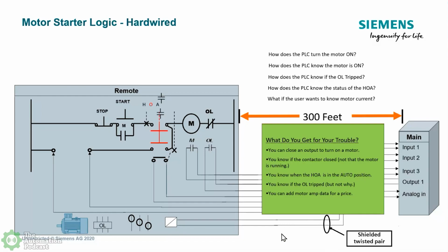So in the case of a conveyor belt, your Lovejoy coupler might have sheared, the motor's turning, so everything's fine because he sees current flowing. But is it truly turning the application that you've connected that motor to? So let's say that Lovejoy coupler sheared and the motor's turning fine, the operator's sitting there happy-go-lucky, but then what do you do for feedback to verify that that entire belt or that entire conveyor is moving?